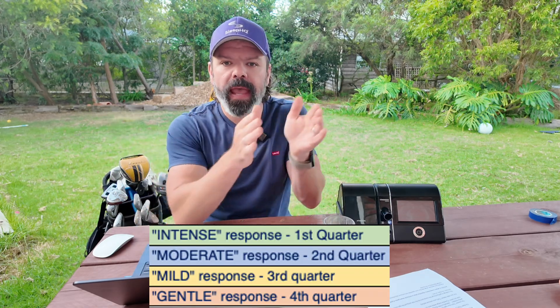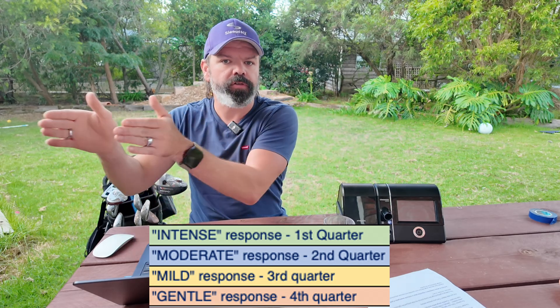This is where Loewenstein plays a really smart game of golf. It breaks your pressure range down into four quartiles, and the pressure delivery from the device dynamically changes depending on the quartile that you're in.